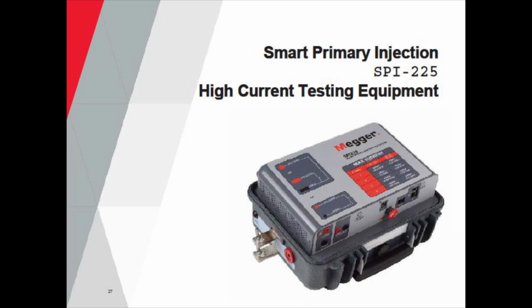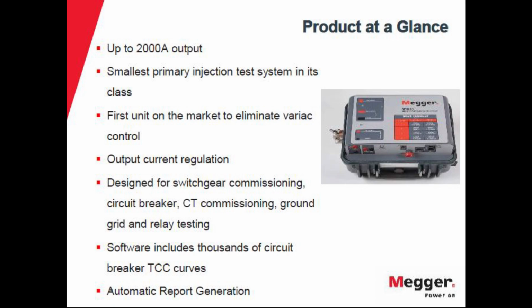This is what we call the smart primary injection unit, 225. That means it can test breakers up to 225 amps nominal current, and for that, it can output up to 2000 amps. We have the unit down there. It's probably the size of this layout. It's a little bit heavy, but for the amount of current it can put out, it's a very light unit compared to other options in the market. It's the smallest primary injection test set in the market.